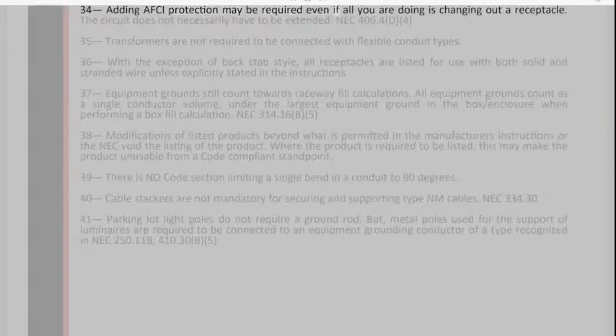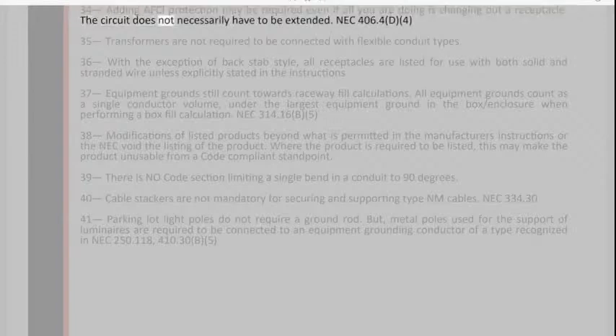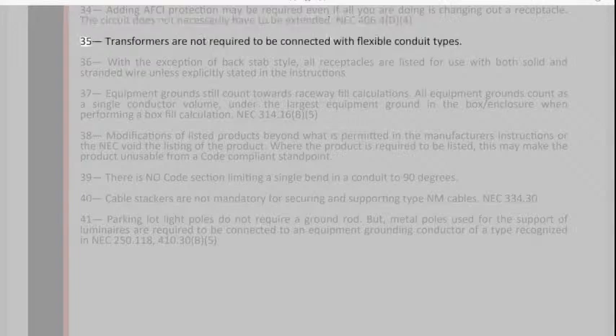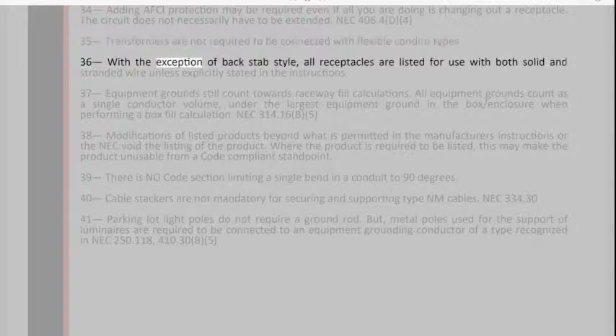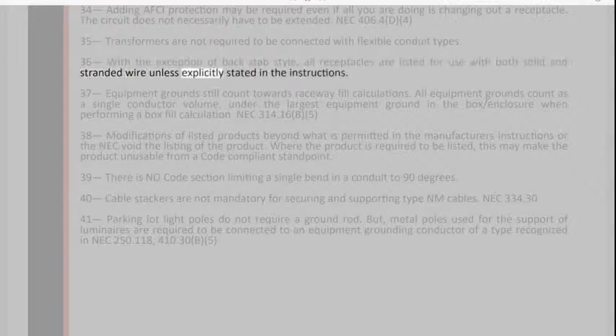4. 34. Adding AFCI protection may be required even if all you are doing is changing out a receptacle. The circuit does not necessarily have to be extended. NEC 406.4 D4. 35. Transformers are not required to be connected with flexible conduit types. 36. With the exception of backstab style, all receptacles are listed for use with both solid and stranded wire unless explicitly stated in the instructions.